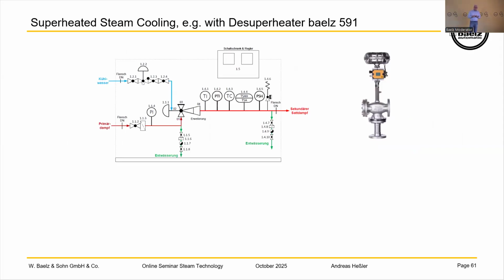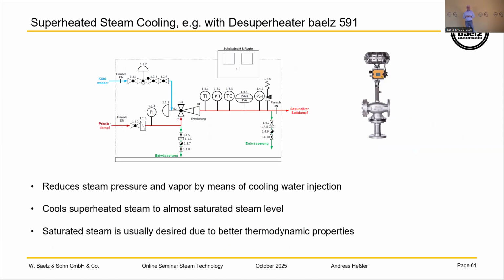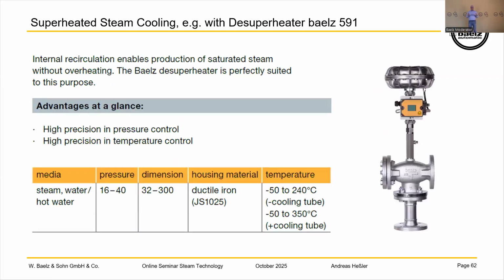Superheated steam cooling with our desuperheater 591. It reduces the steam pressure and temperature, and instead of only reducing the pressure, it injects water. This cools the superheated steam to around saturated steam level. And like we already discussed with Michael, it is always good to have saturated steam for the heat exchanger. So when you have superheated steam, you can reduce it to what your application needs for pressure and temperature, near saturated steam temperature. Here is just a quick overview of the sizes and how we normally do it.